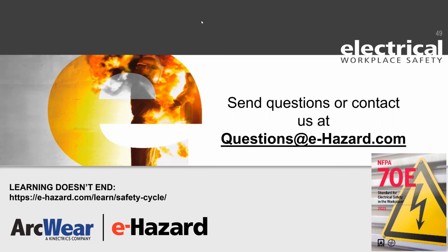And now I understand that OSHA is a little bit vague in their requirement, but basically what it says is that the employer shall actually look at all of the equipment that they've got installed using the principles conveyed in what is an arc flash hazard, what is a shock hazard, basically go through this. Now, changing a fuse is a very common one. We've just completed an accident investigation where a worker was replacing a fuse on a bus duct. Folks, these are those installations high up in the ceiling on the roof, and you have a plug that drops down from it.